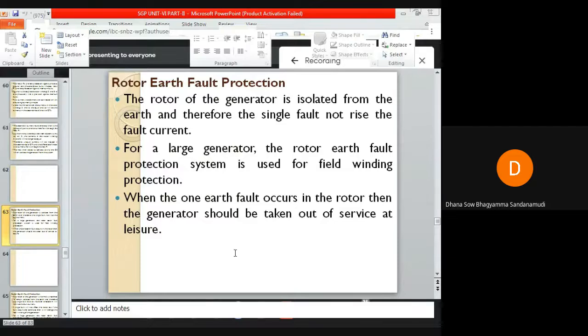Now let us discuss one more type of protection, that is rotor earth fault protection of the generator. The rotor of the generator is normally unearthed, isn't it? The stator will be earthed, but the rotor is unearthed; that is, it remains isolated from the earth. Therefore, if insulation breakdown occurs in the rotor, it will not lead to any fault current. There will not be any leakage of fault current from the rotor to the earth, because the rotor is isolated from the earth.